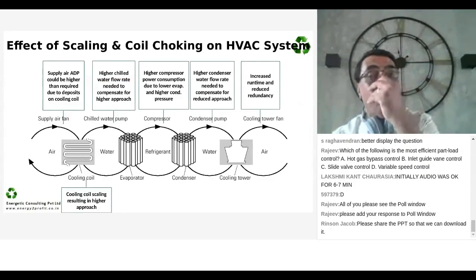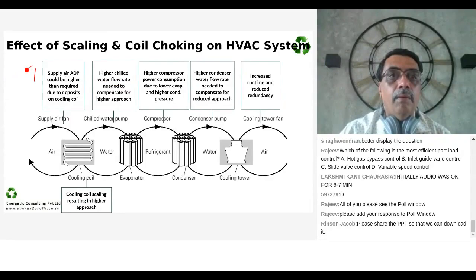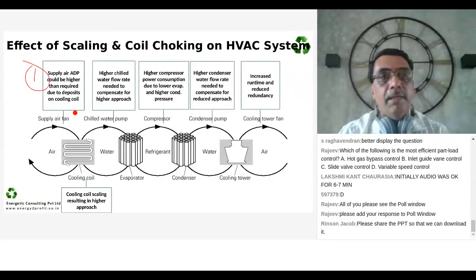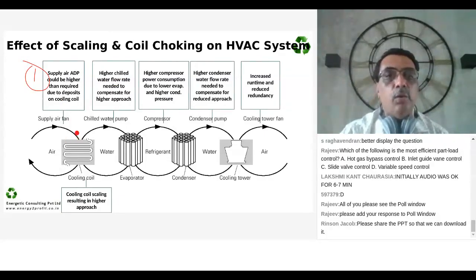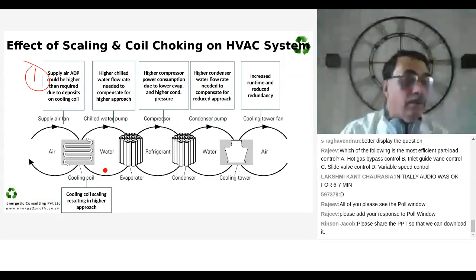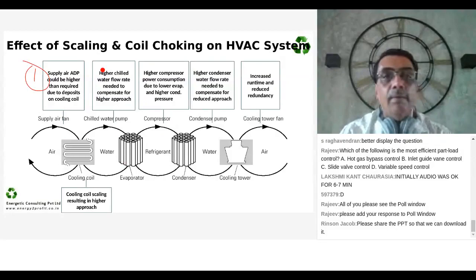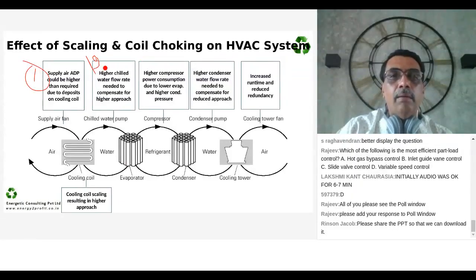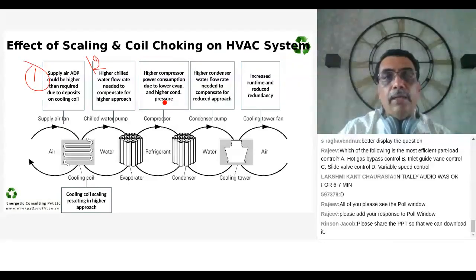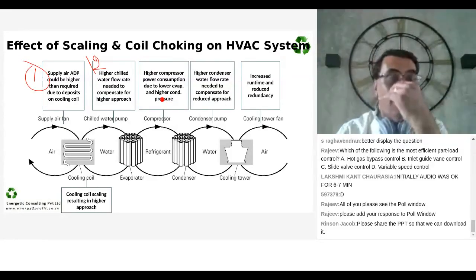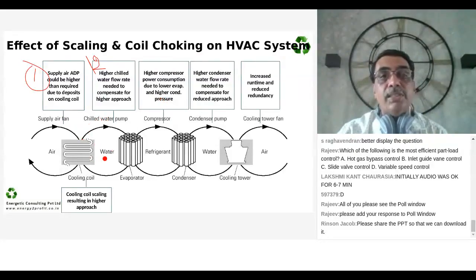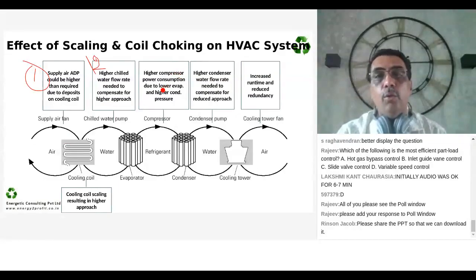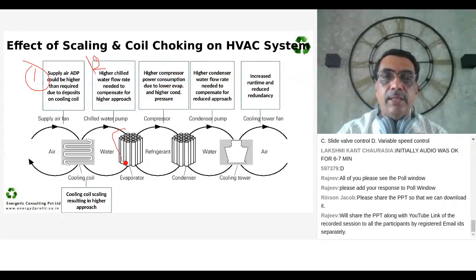You have a symptom checker. When the supply air ADP is going higher than the required, this could be deposits on the cooling coil. This will tend to increase your humidity in the conditioned space. When you require lower temperature of chilled water and or higher flow rates, you may say that the exchanger is choked, the AHU is choked. When your compressor power goes higher due to lower evaporating and higher condensing temperature, you can say that these exchangers are choked. That is the evaporator and condenser.